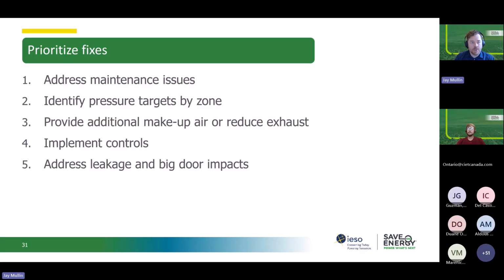And number 5, addressing leakage and big door impacts. This one should be done last, because if you start fixing these leaks and infiltration issues before addressing the air balance issues, that can make the problem even worse, because you're restricting that flow and even increasing that pressure differential as a result. This can include things like improving seals and using air curtains on loading bay doors. You may also consider a local makeup air unit in loading bays to reduce air infiltration and maintain comfort there.